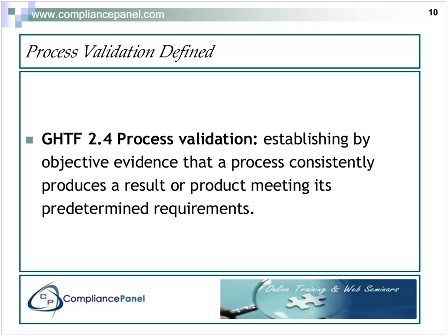In the end, the manufacturer is responsible for the process validation that is required for that particular product. So we may, in some cases, rely on a supplier to perform the process validation and provide this objective evidence for us that we must have on hand to demonstrate to the FDA that this has been completed.